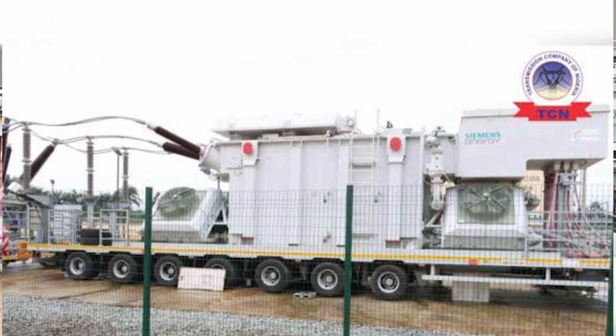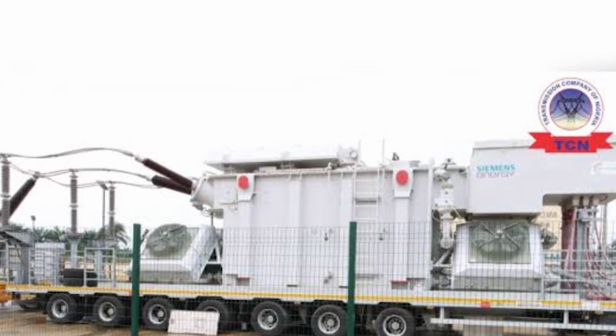But with the introduction of this 63 MVA transformer with 4 feeders radiating out, presently we have 2 feeders. The ones coming from Owerri substation will now be broken at some point, while this one will serve these other 2 areas. Subsequently the other 2 feeders will come online, easing the burden on Owerri Works Center, and these other places in and around FUTO will have steadier power because they are now closer to the source.